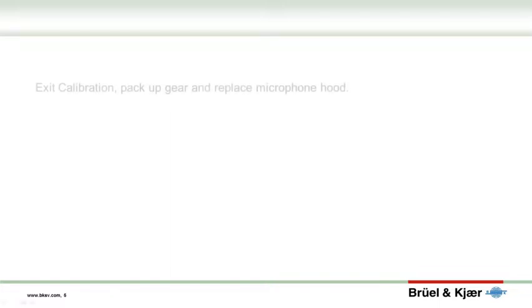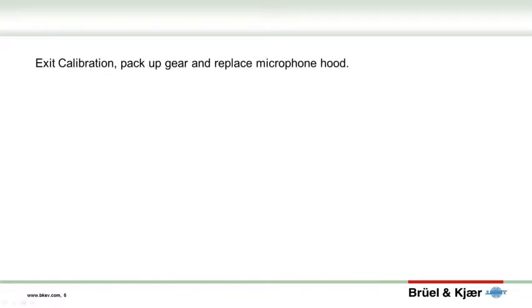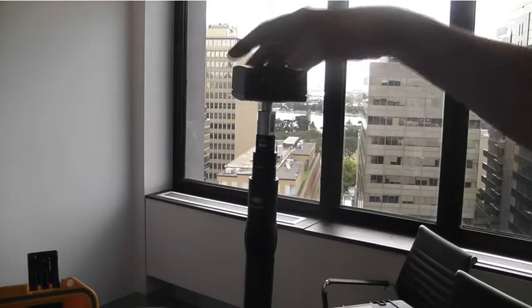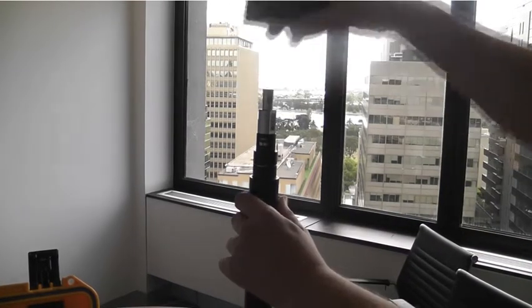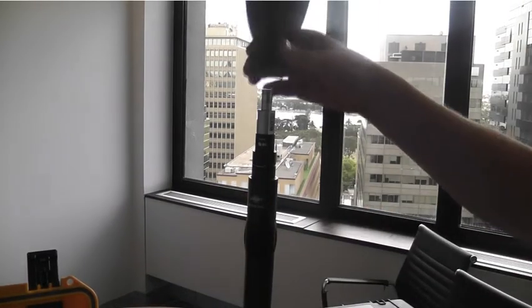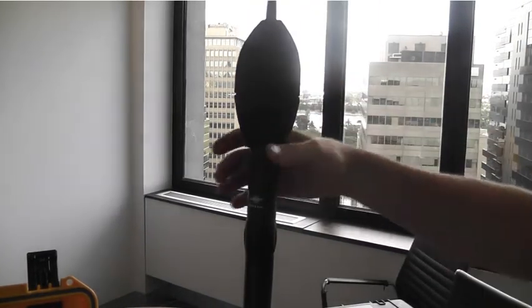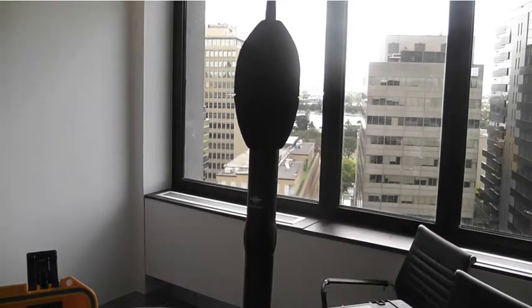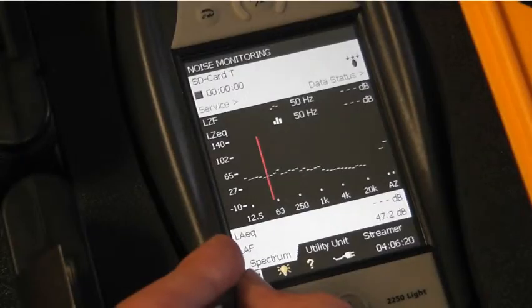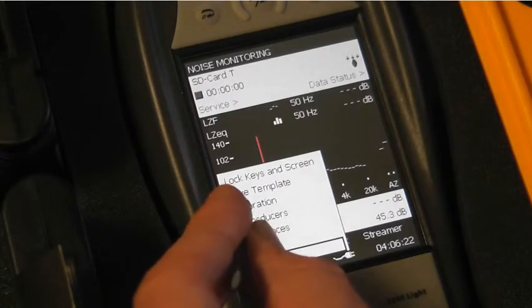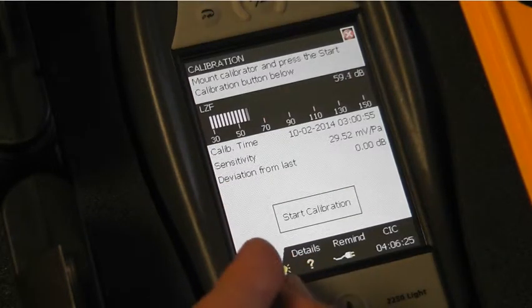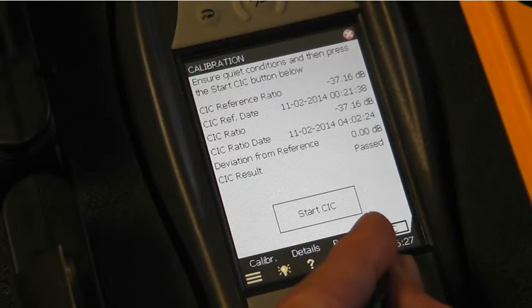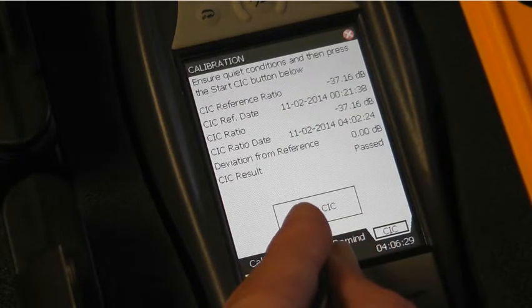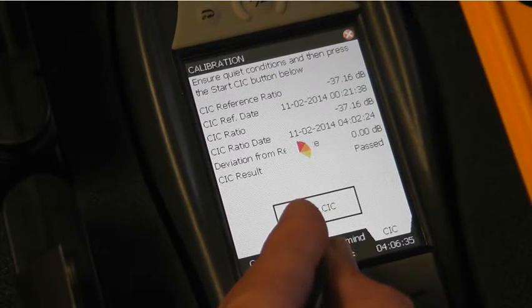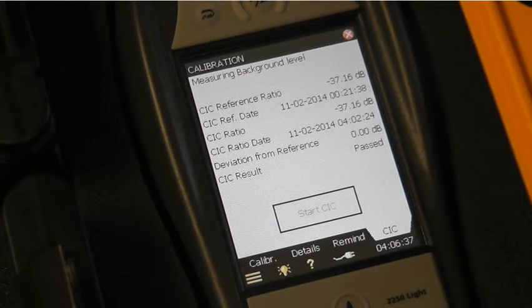Once that's done, exit the calibration menus, and turn off the calibrator and reassemble the microphone. You'll need to follow up the acoustic calibration with the Cic calibration. Doing this will send the corrections to the Sentinel client and finish the process. Cic calibration requires a quiet environment, so you may decide to perform this step before going to site.